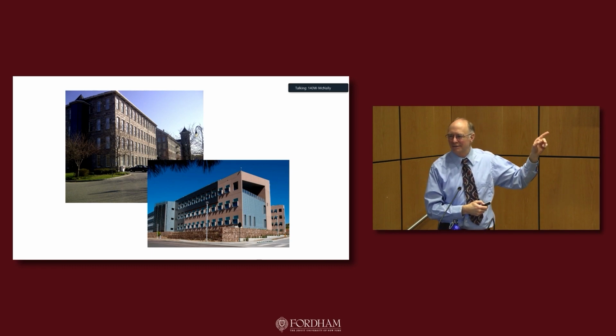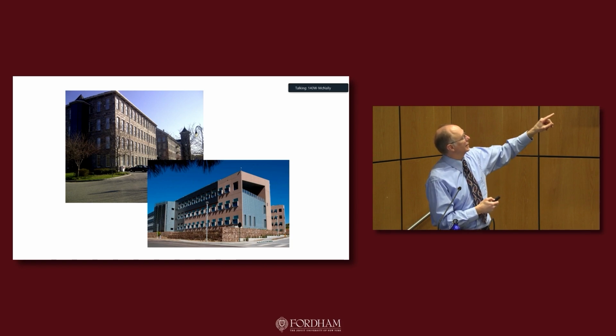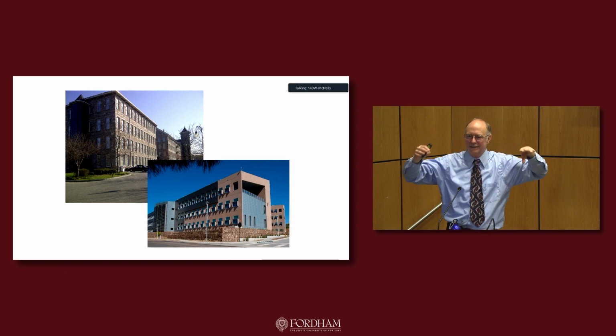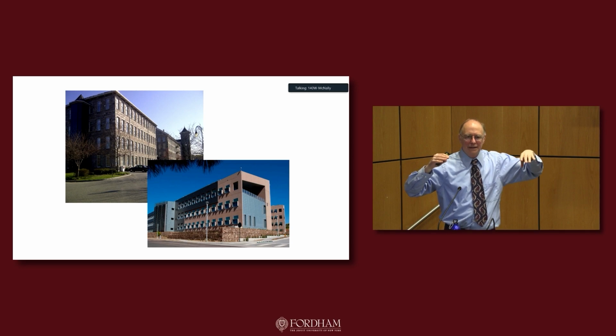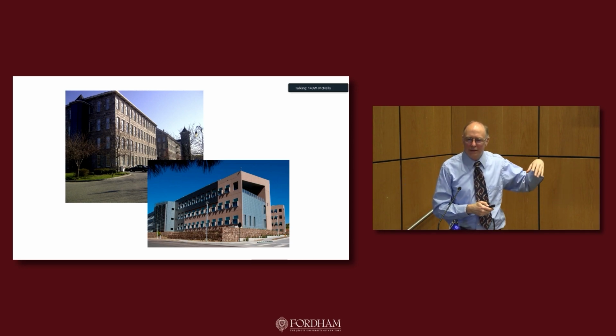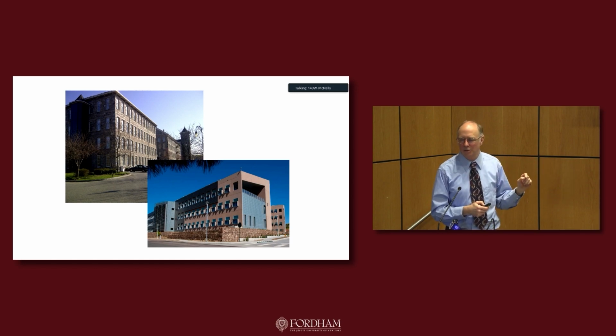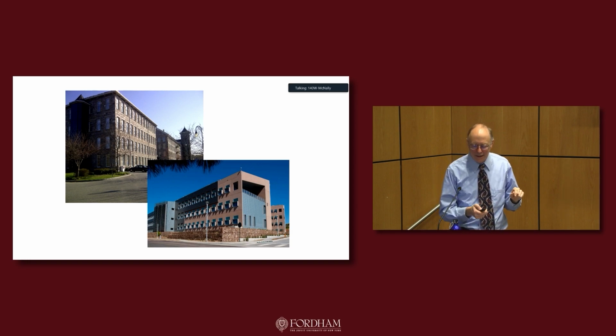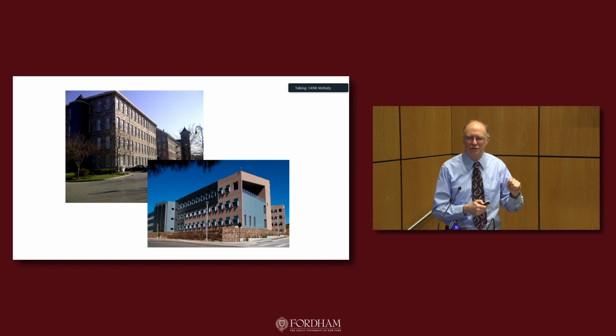Notice how the building in the lower right, very similar, a little more sophisticated, designed with computer models, has the daylighting glass at the top. It's got natural ventilation in those little hoods, which protect it from the high summer sun, and all the glare inside is controlled. That building's first phase is 240,000 square feet. Normal daytime lighting load is about 10 kilowatts for 240,000 square feet, so you can do the math. Huge amount of energy savings in the lighting. And by doing that, what happens to our cooling load? It goes to near zero.